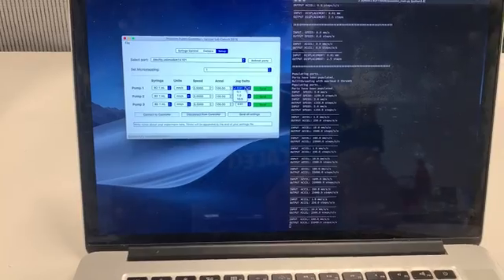Another cool feature is that I can pause and resume the syringe. Let's set all displacements to zero except for syringe one, and move syringe one back 20 millimeters using minus 20. I'll press Run and then Pause, which will pause the syringe sled, and then Resume to continue it. So: press Run, pause it, and resume it.